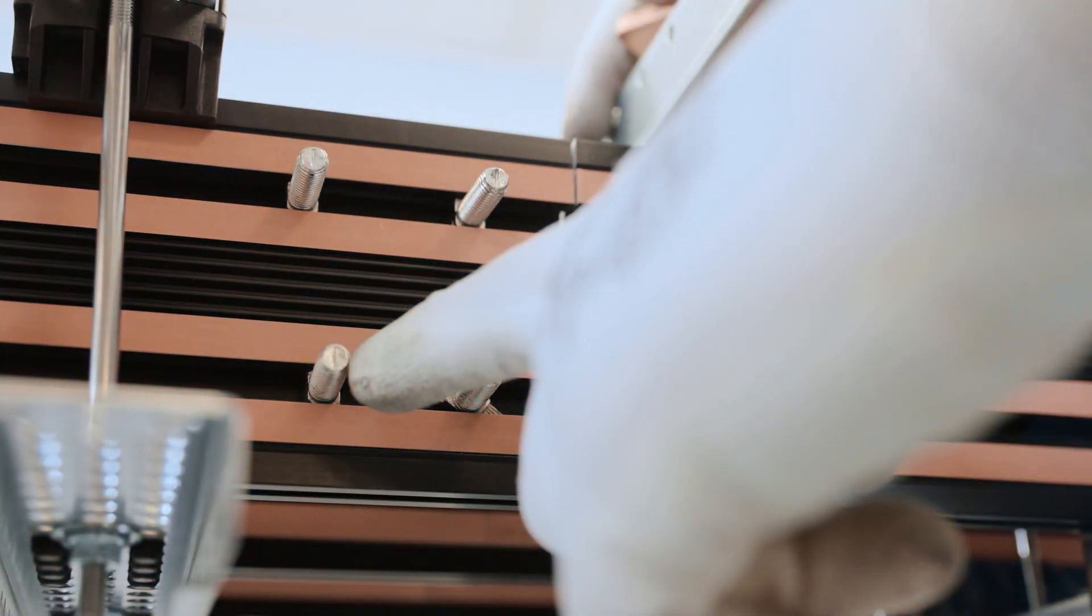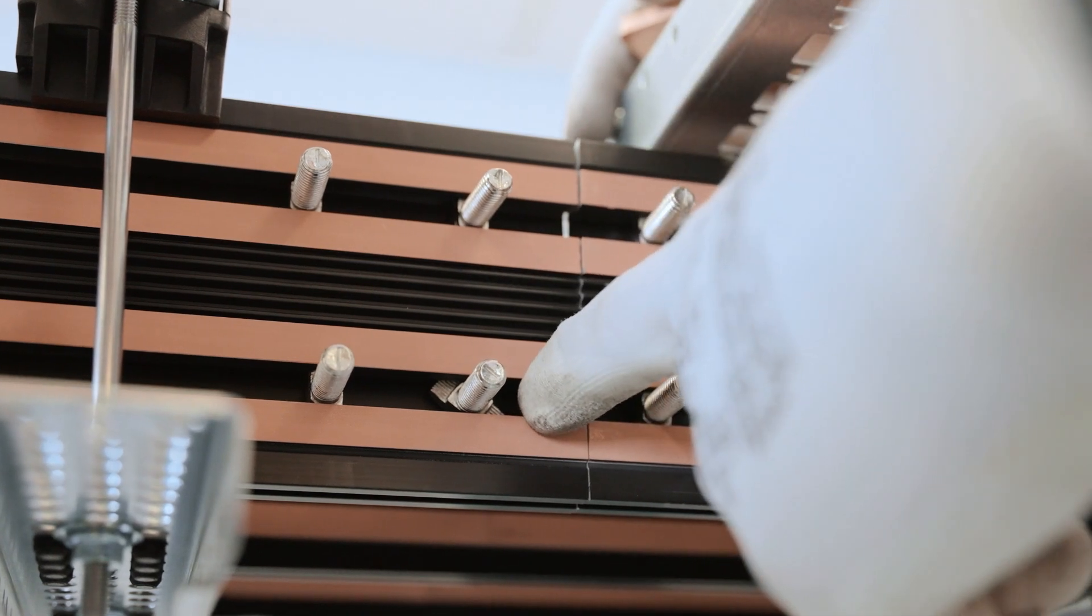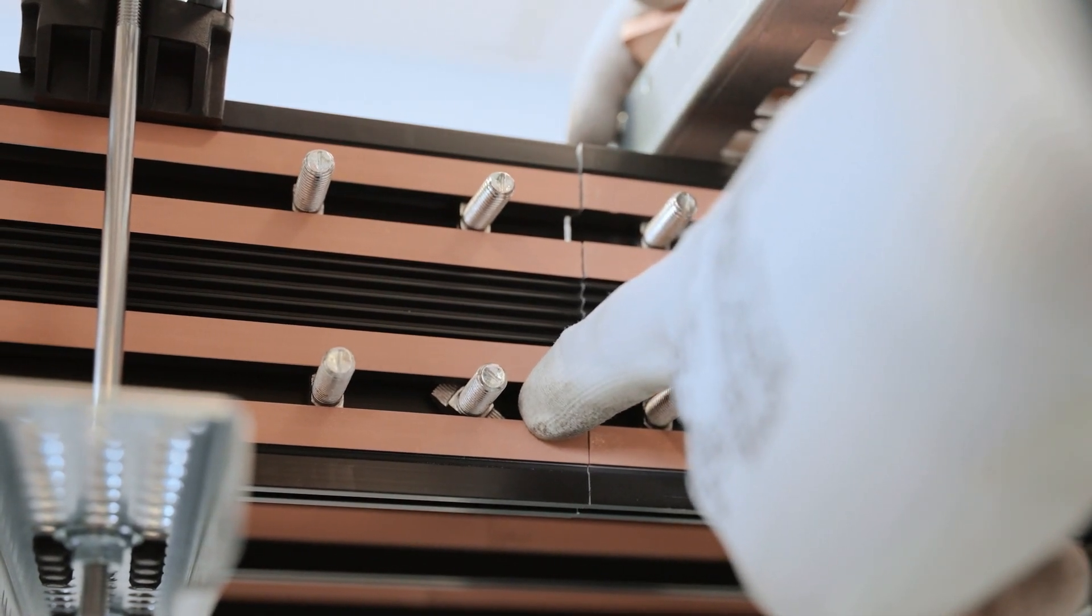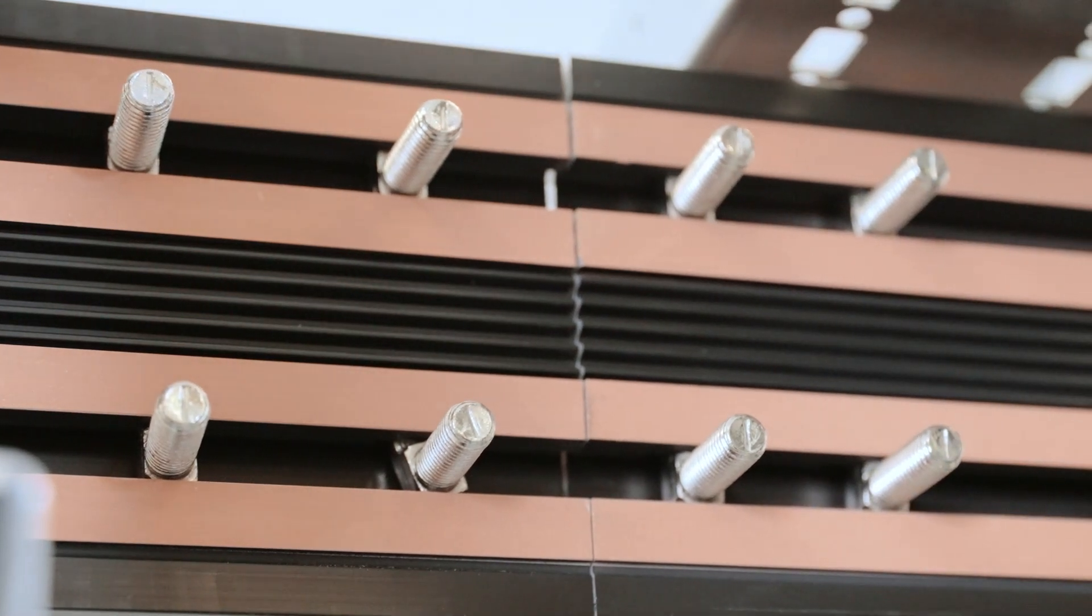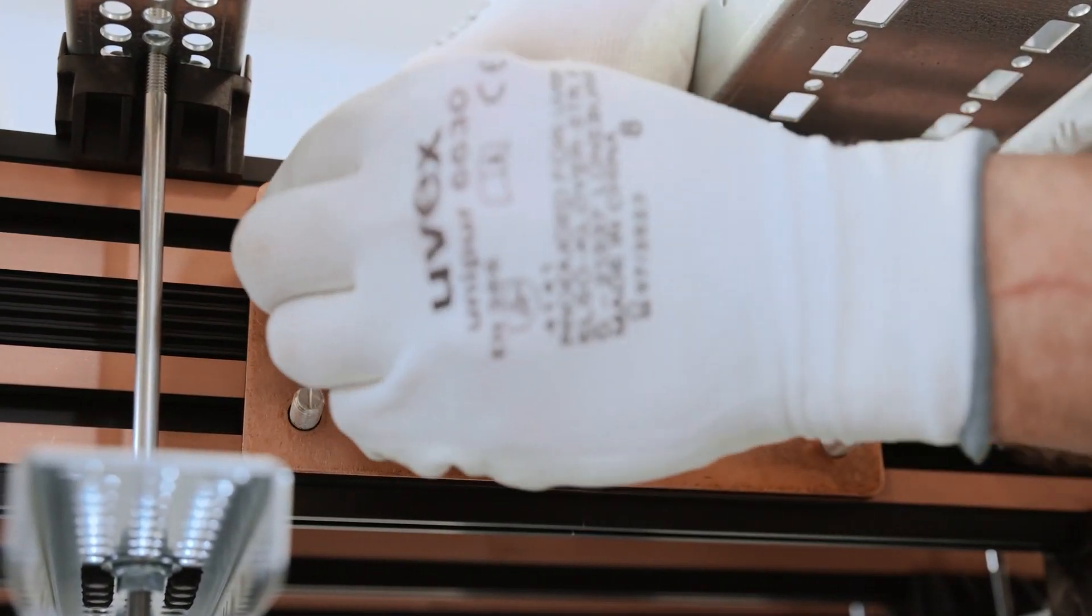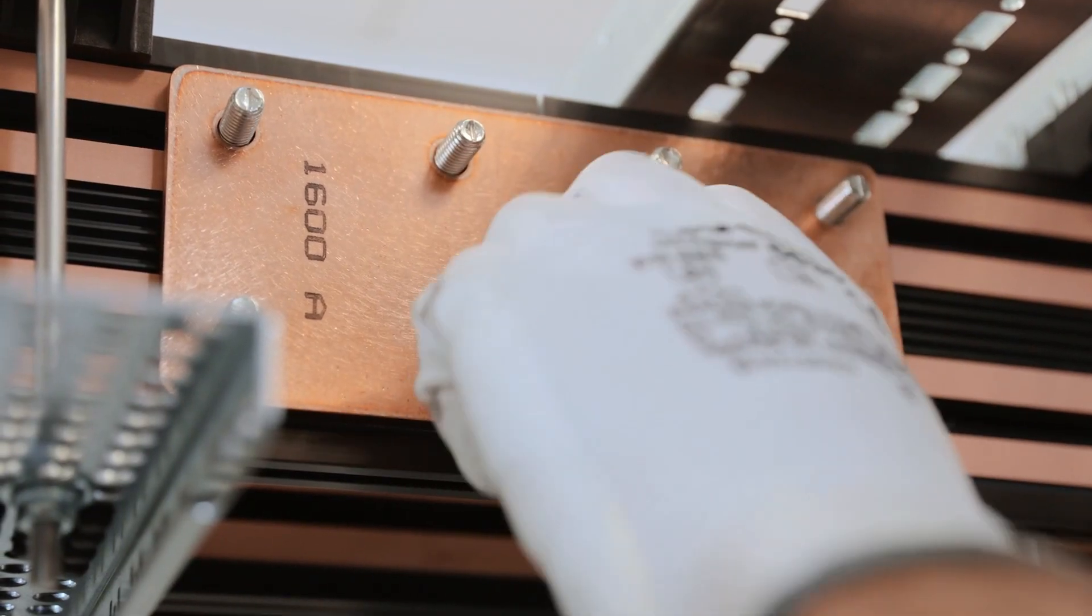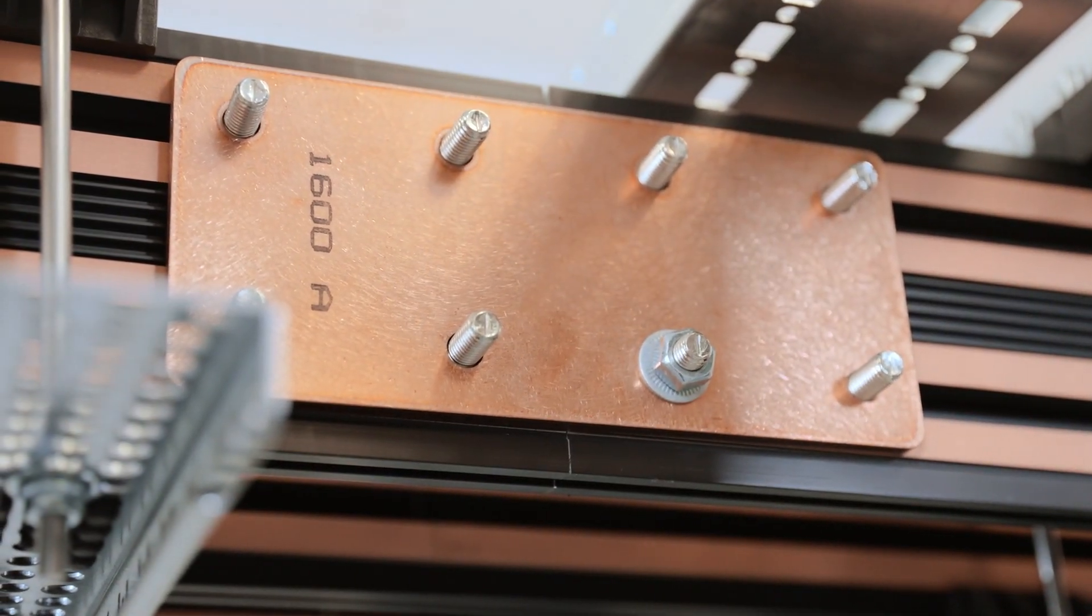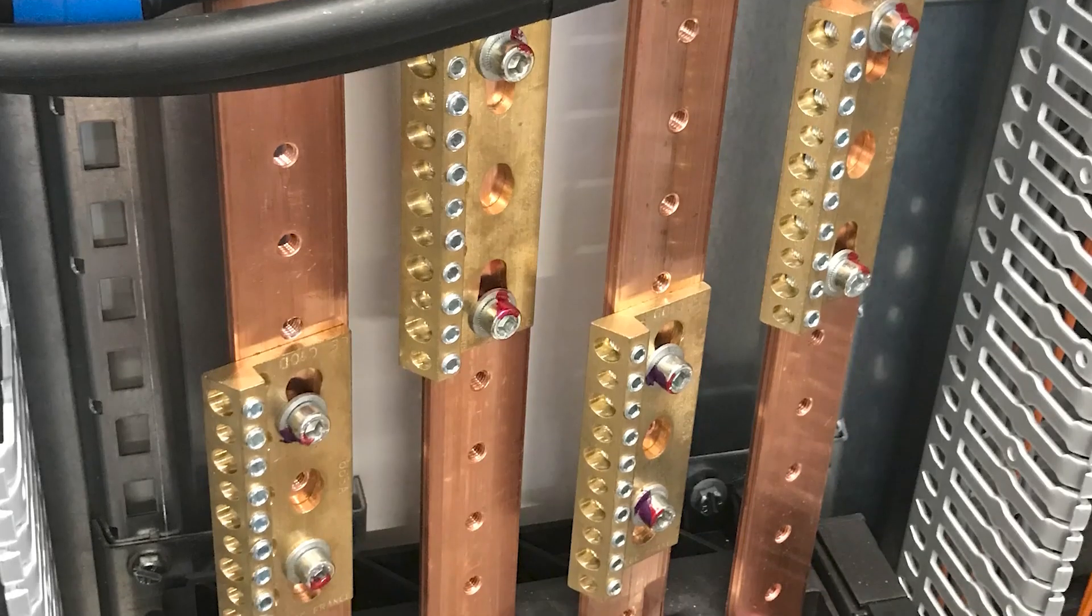With the hammerhead screws, position of the connections on the aluminum busbar is freely selectable. Before tightening the nuts, it's important that every screw has been turned full 90 degrees. Check all indication slots, slide in the plate, check if the screws are still oriented vertically for wiring.